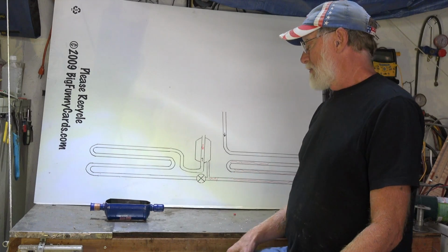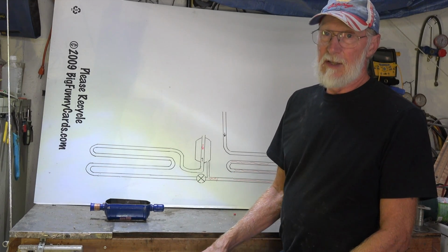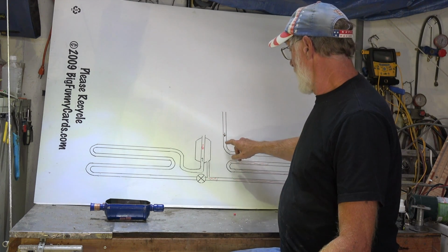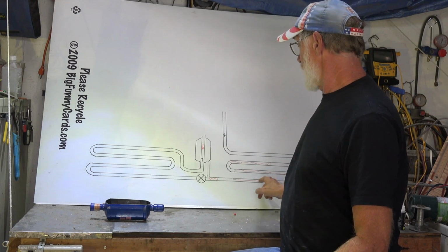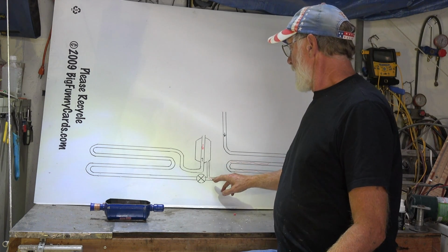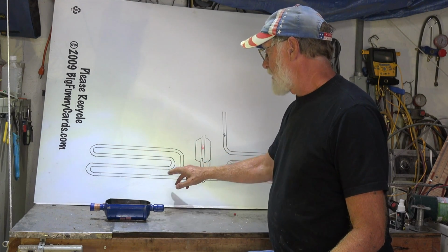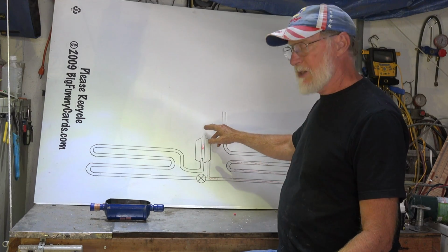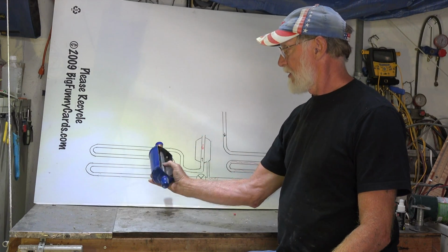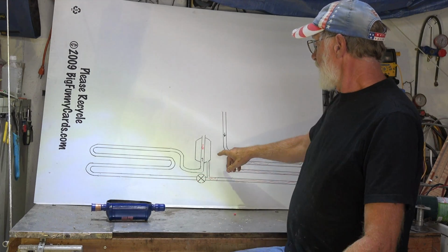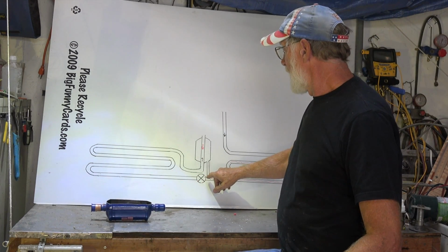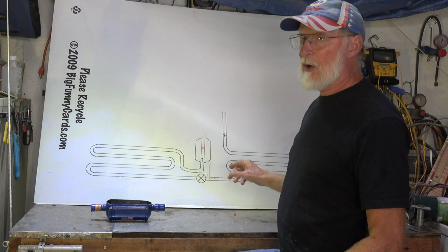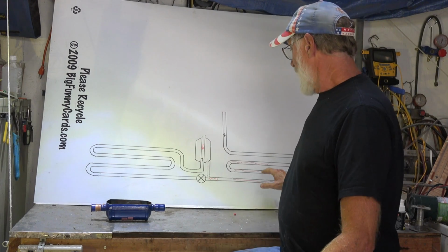Okay, it's a pretty different device than the receiver. So when this thing is under operation, hot gas comes in here, turns into liquid, then passes through the expansion device to the evap here, with superheated cold gas coming through here. That's that central pipe right there. And the tap coming from the liquid line goes up into here, and because it's cold, it moves in there.